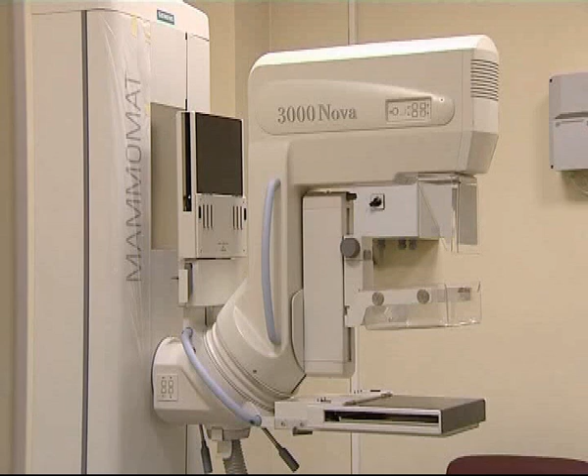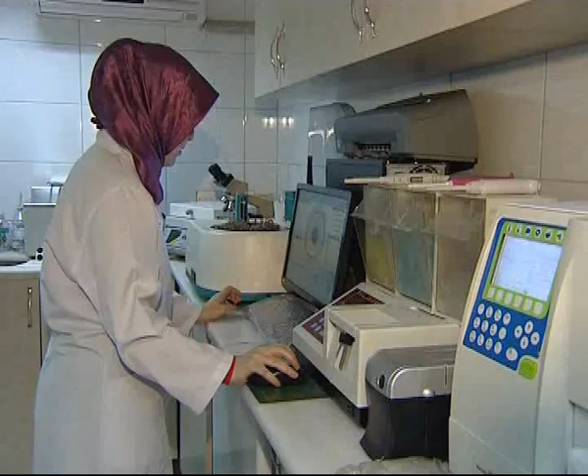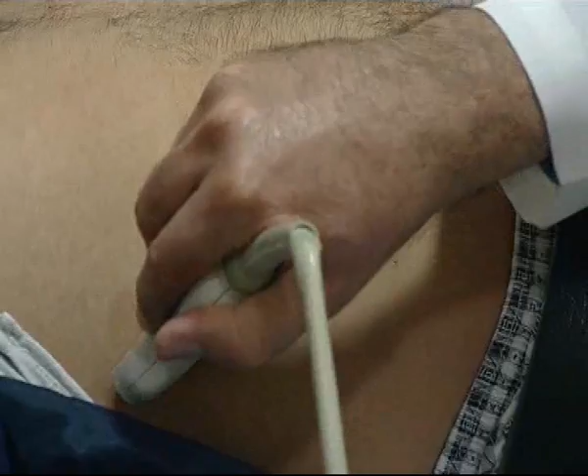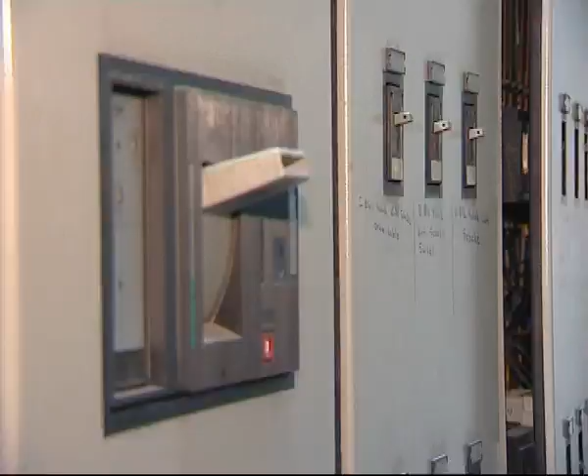It is connected to fuse outlets that feed each life support unit, fuse outlets of the secondary panel feeding intensive care and laboratory systems, fuse outlets feeding each tomography, ultrasound and X-ray machine, and to the outlet of the power plant's feeding power switches, to protect against overvoltage shock given to the system as a result of removal of power plant load when electricity power is cut.